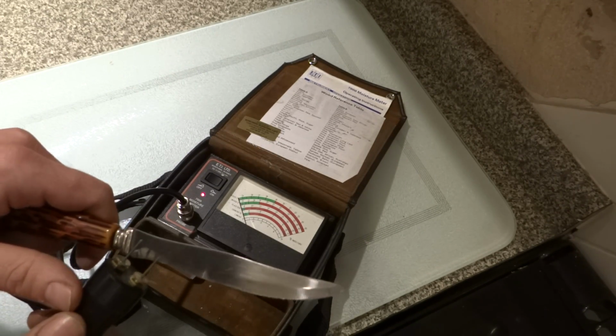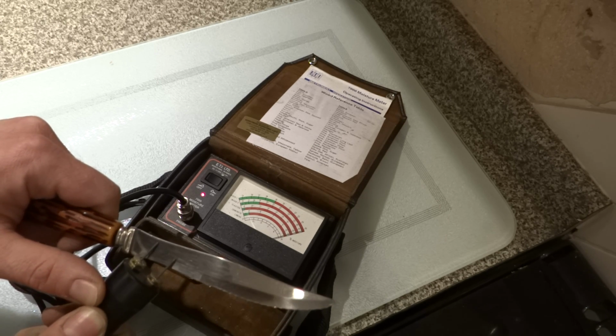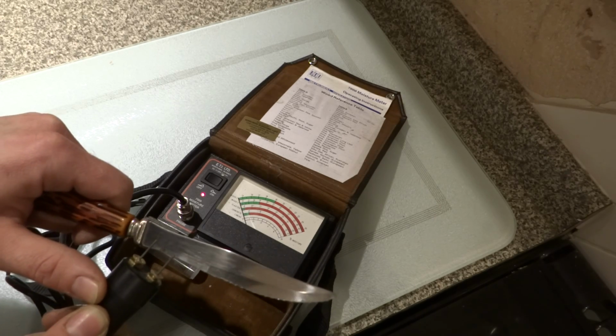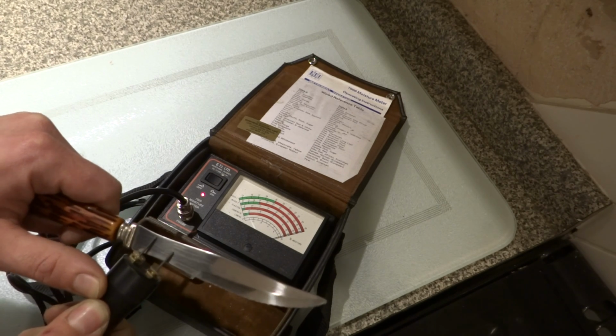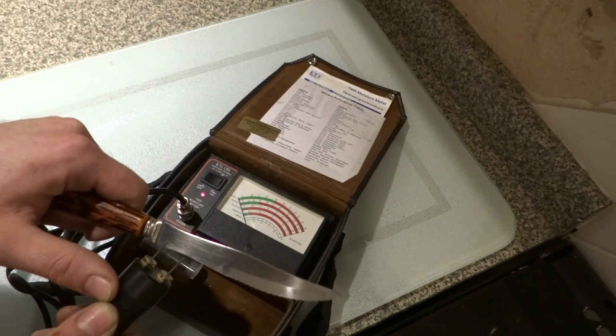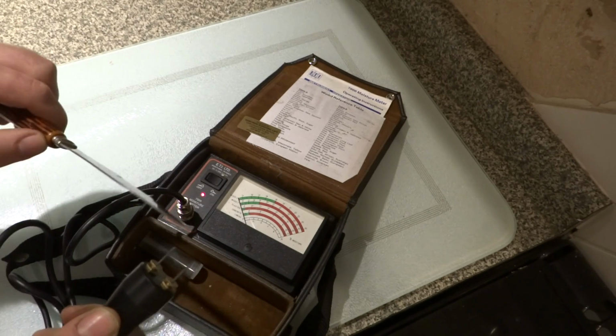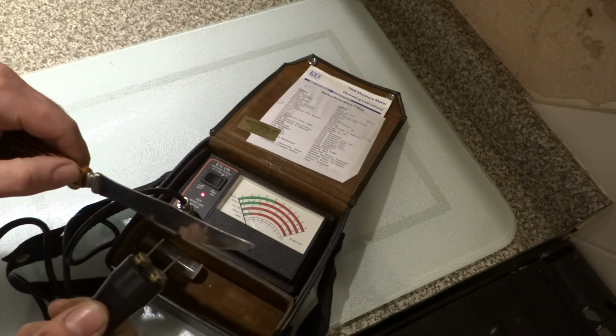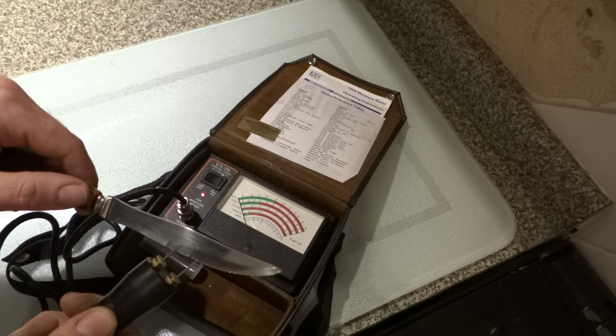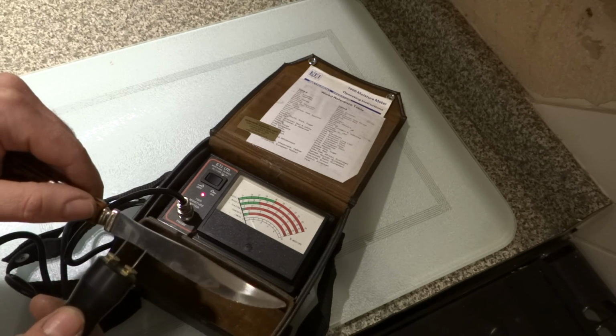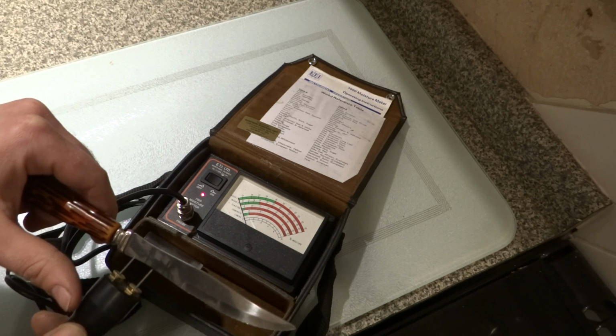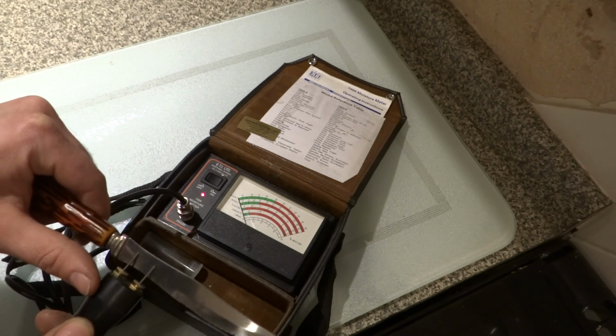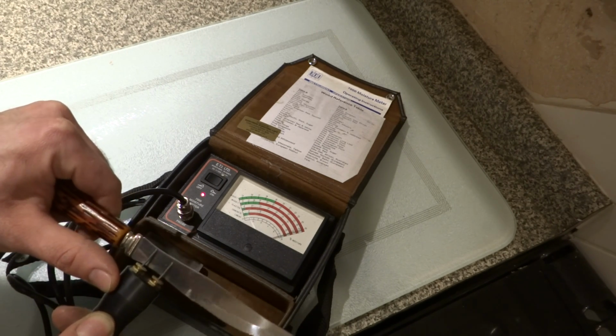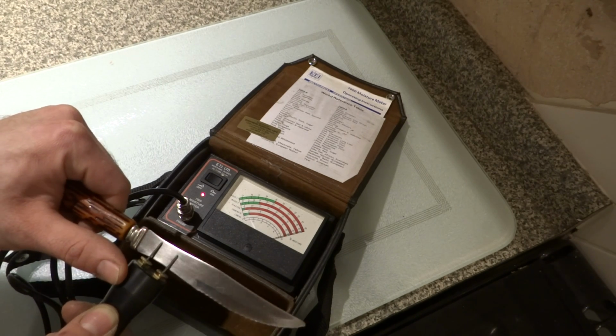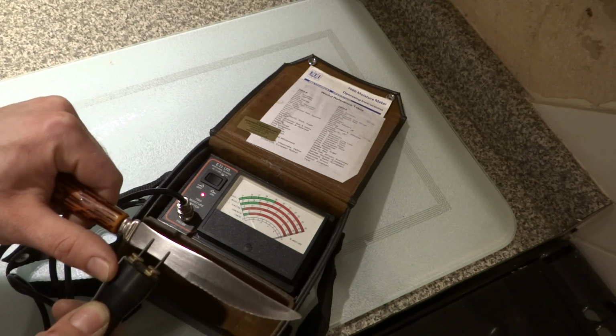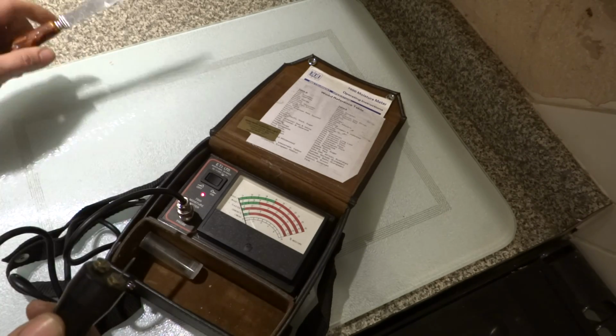Now we're going to just short out the probe essentially. As you can see, the scale's gone right across. We'll do that again. So I'm assuming if you're looking at this you know how they work, but they measure the moisture by putting a current between the two probes and measuring some feedback off that. So by shorting it out on a conductive object, we're proving that to some degree that they're working. So we'll just do that again. Okay, quite happy with that.